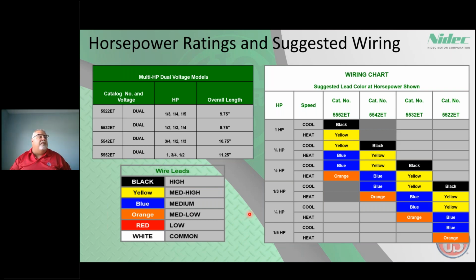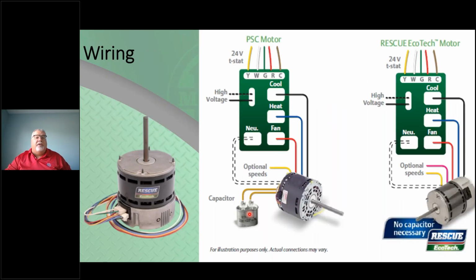The wiring for the contractor is very simple. Here's your PSC control board, high voltage in, here's your cool, heat, and fan, and here's your capacitor. Come over here, it's exactly the same hookup - cool, heat, fan, no capacitor, and you're ready to go. Basically this motor takes that high voltage signal, and it knows exactly, because the black lead is being energized, that it's going to run at the highest speed.